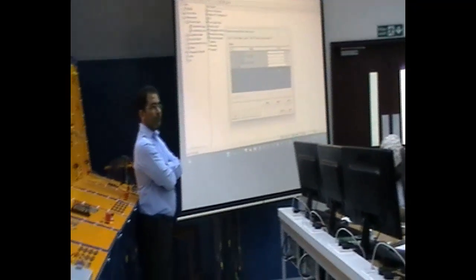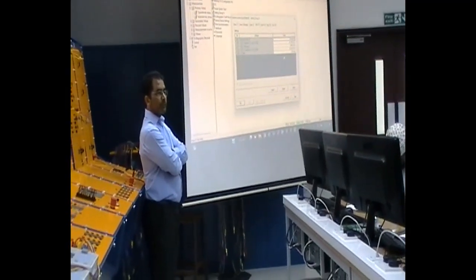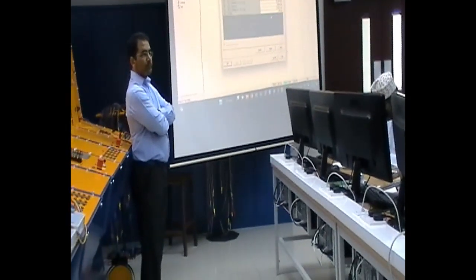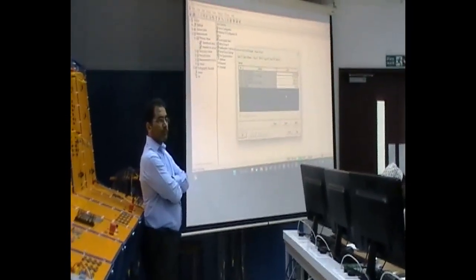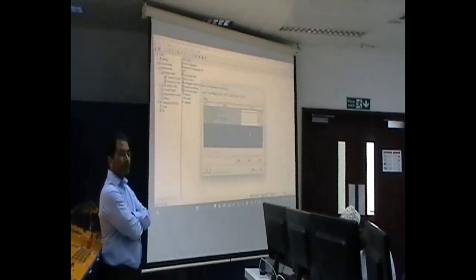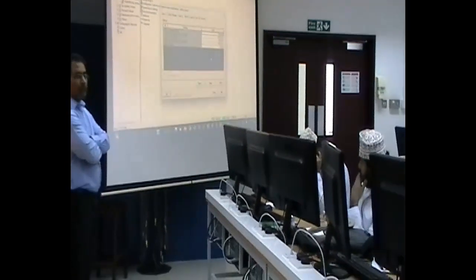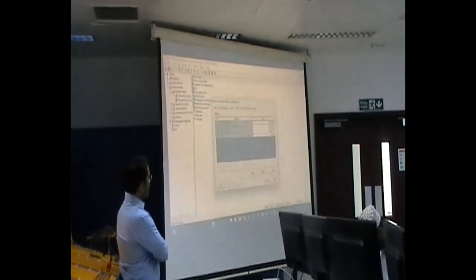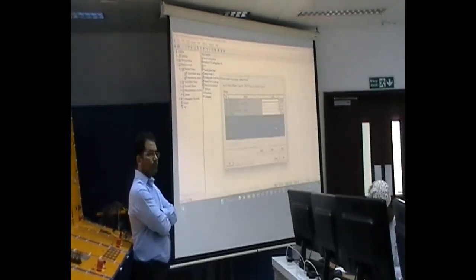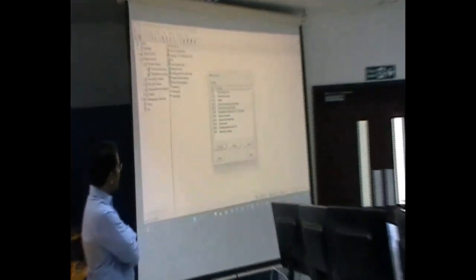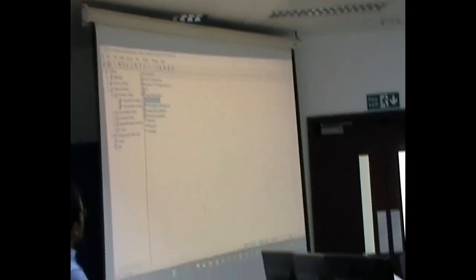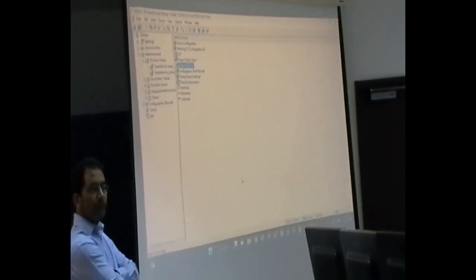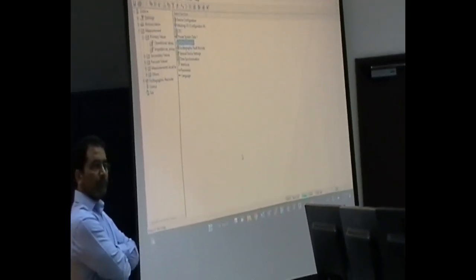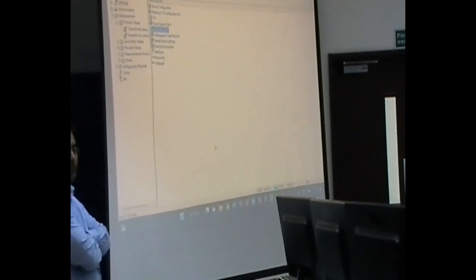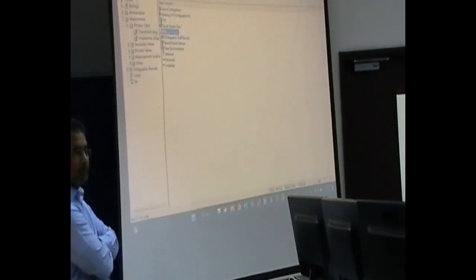But because this is a very backup protection for very far away substations, like reaching from the relaying point several kilometers, plus it goes to transformer and bus bar and other loads. So now we've got all the data we need. We can go through the test. I don't need the relay software for the testing. I always need it to download whatever I want from the relay, or to make change here and send it to the relay. But the testing software will be different. But I'm gonna use it today for the measurement at least.